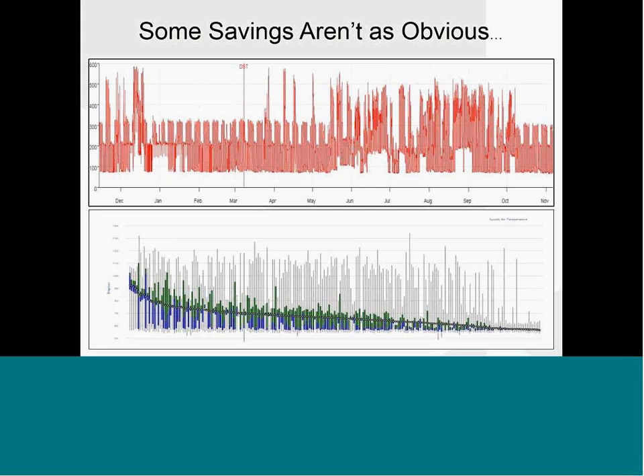So this is what I'm showing here. If you look at the lower chart first, there's a VAV box that's hunting around, trying to settle around, I think, a 50-degree temp there. When you have a box that's hunting like that, it's causing cycling equipment, you're losing energy, and maybe even comfort issues — you can probably hear it in the room where that box is hunting around. So that's an area you can target for some energy savings.